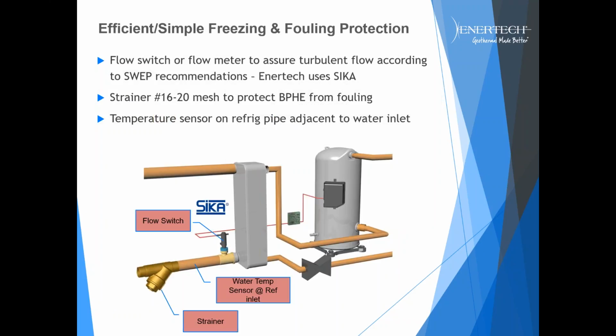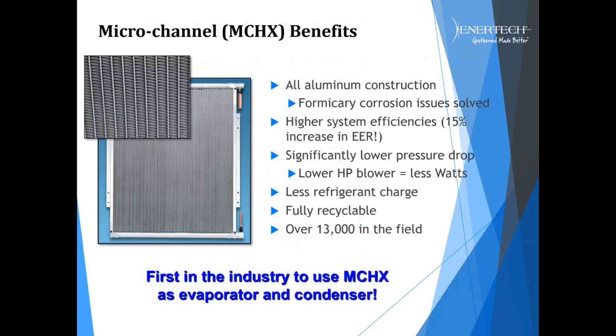And again, you can see here the flow switch and the temperature sensing ahead of the braze plate just to make sure that we're covered. And obviously, we always want to put a Y strainer, a 16 to 20-pound mesh Y strainer, in to protect it from fouling. Okay, moving on. That's really it from the braze plate side of it.